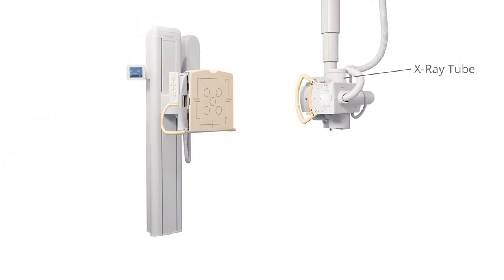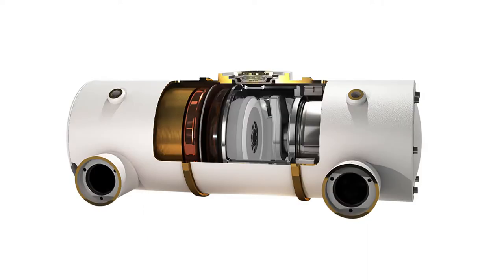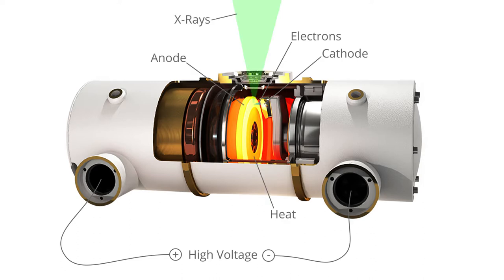A typical projectional radiography system consists of the following main components. The x-ray tube is what produces the x-rays. It is a vacuum tube which applies a high voltage to accelerate electrons released from a hot cathode to an extremely high velocity. These high energy electrons collide with a metal anode producing x-rays.